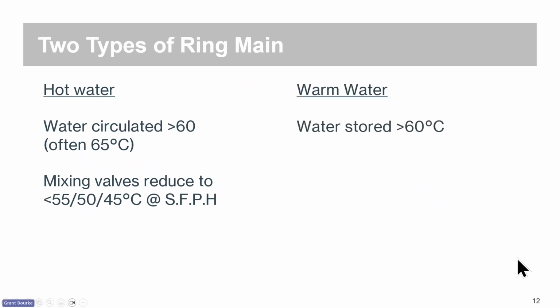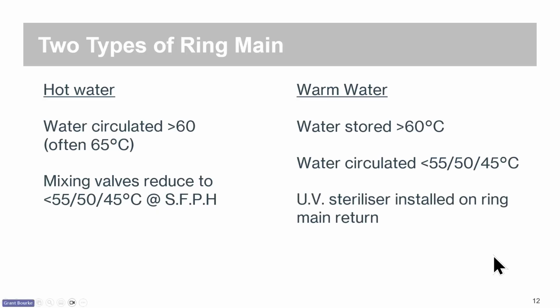We've also got warm water ring mains where we're still going to store any water at greater than 60. We're going to circulate the water in the whole ring main at a lower temperature, so we don't need to mix the water down at the branch offtakes. And any water that we recirculate, we're going to put through a UV sterilizer, and we'll have a look at that in a minute.